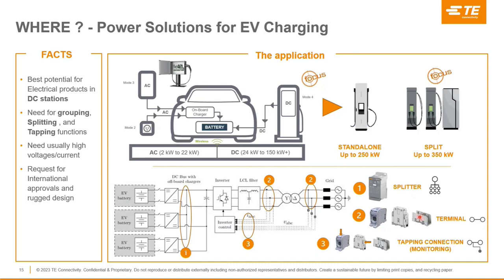Second, you need power connections, as Abhijit mentioned before. You have different ways of doing it: compact power blocks if you need space, standard SNK series thermal power blocks for screw connection, or terminal splices with stud-type terminals. Depending on the customer's solution, you can propose different technologies to connect the power parts from the grid or from the output of the inverter, where most of these products are represented.